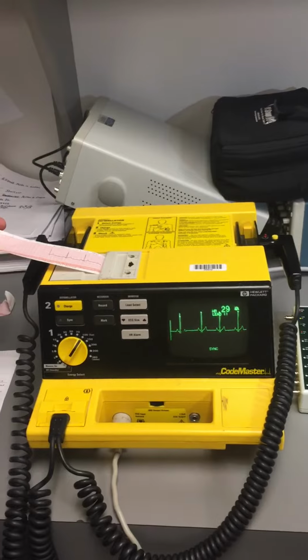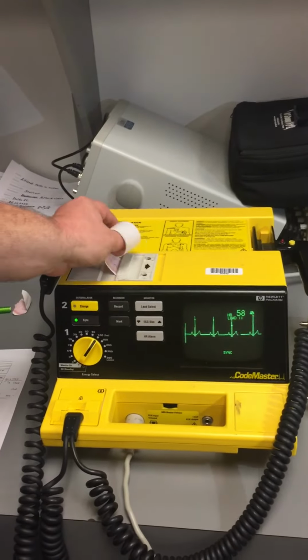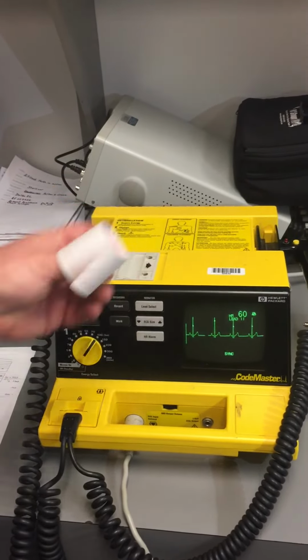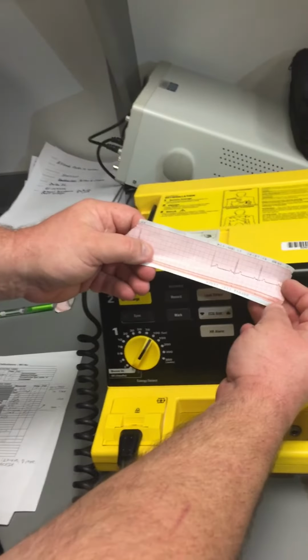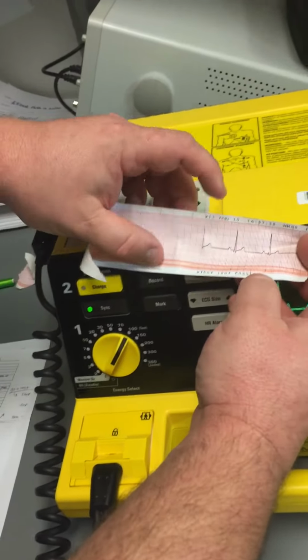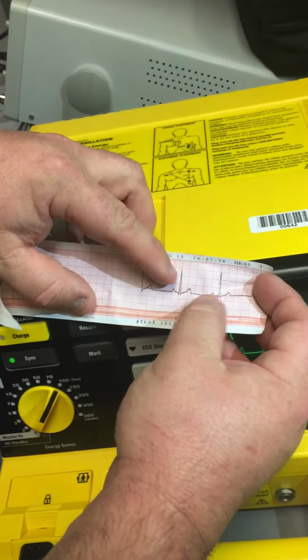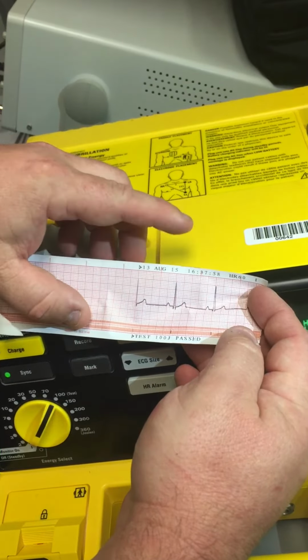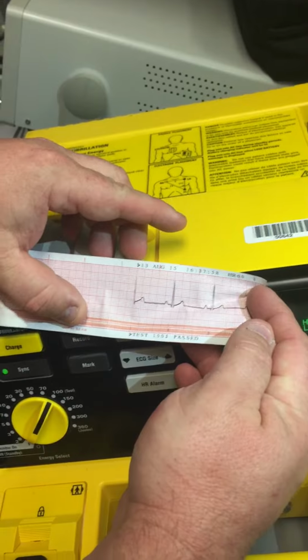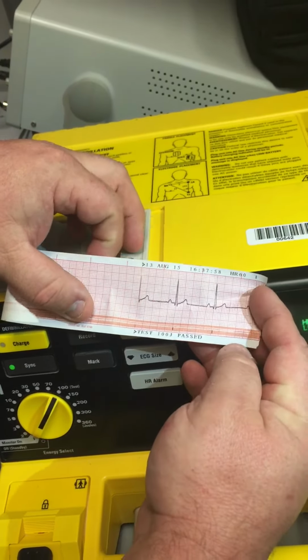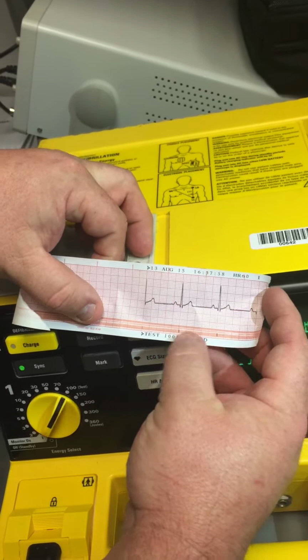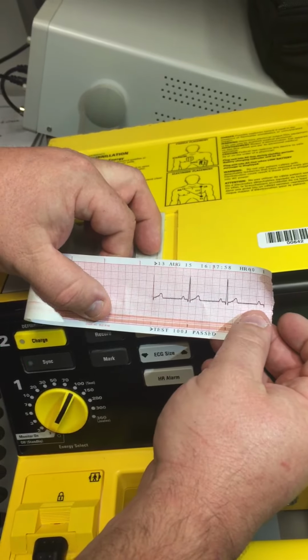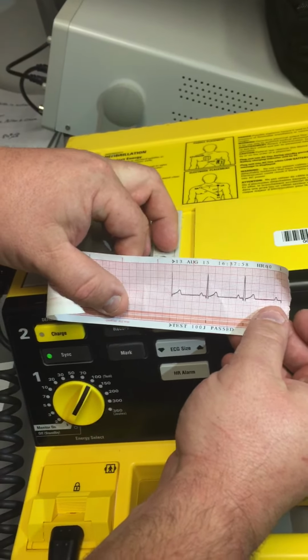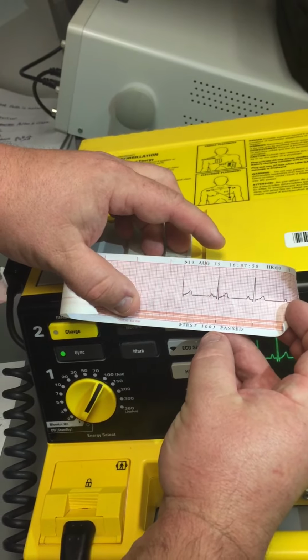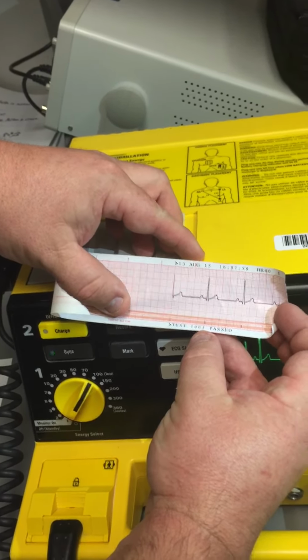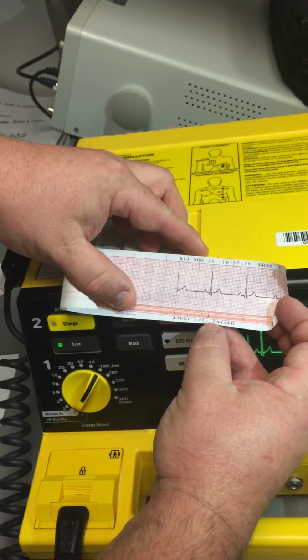I left the sync on, so I had to hold it extra long. If you look at the strip here, it's got a lot of very important things on here. We've got the date, we've got the time, we've got 60 beats per minute because I can count the number of squares, and that one's actually perfectly timed. Five boxes are in between each one of the peaks of the R waves, which tells us that we're at a 25 millimeter per second print. And then we've got 100 joule passed at the bottom of this print.